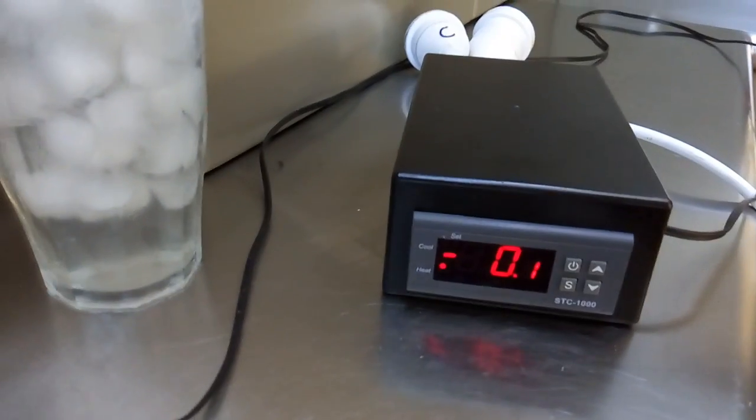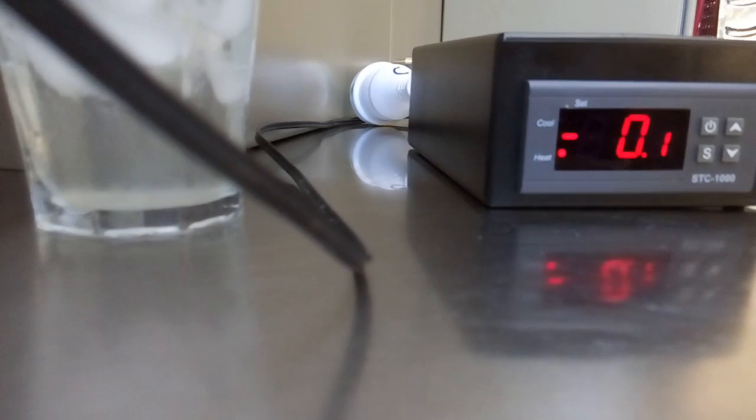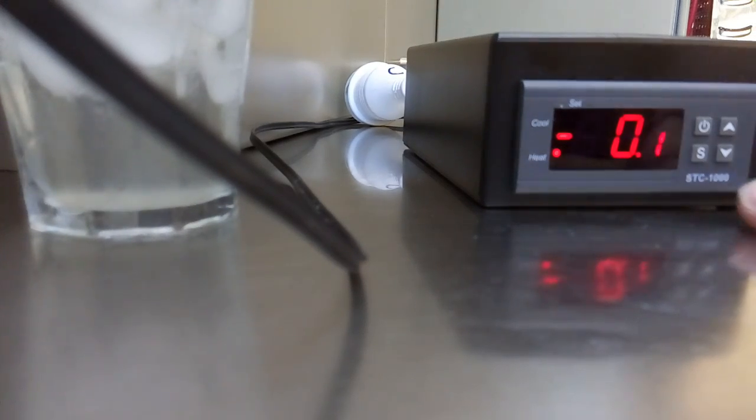Then just wait till the display settles down, which I've done here. You can see that mine's reading between minus 0.1 and minus 0.2, pretty much on 0.1, so I'm only about a tenth of a degree out.